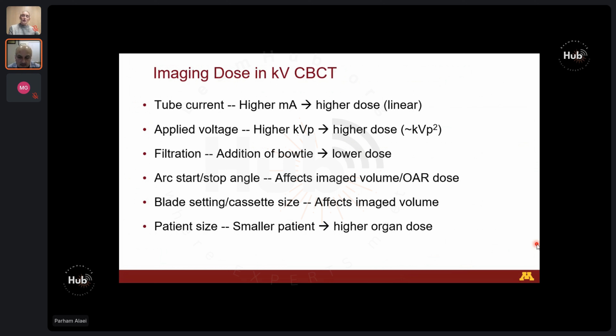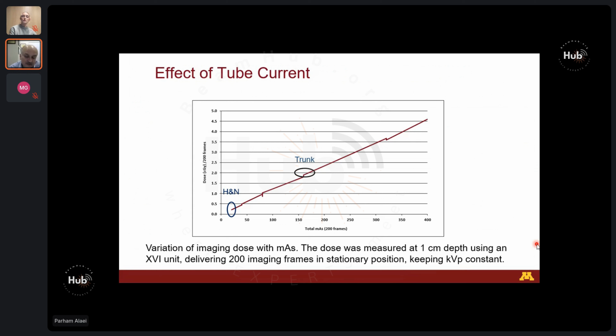And the patient size: smaller patients receive higher organ dose because this is an example of one size fits all. We apply the same thorax or pelvis protocol to all the patients. So smaller patients get higher dose. And again, tube current, this is something we measured a few years ago. We increased the mAs, it was total current, and then compared that to the dose measured in a phantom. For head and neck, we are somewhere on there. For thorax, trunk is somewhere out there. And then we extrapolated that, we measured it higher. We never use anything up here. But as the current is increased, so does the dose.